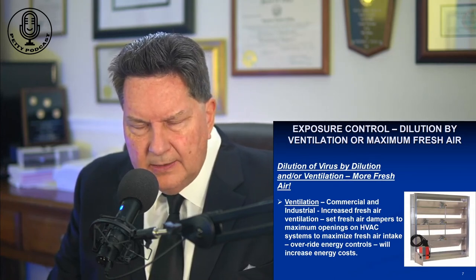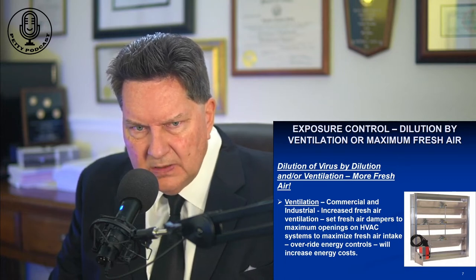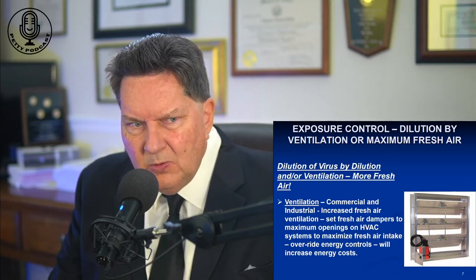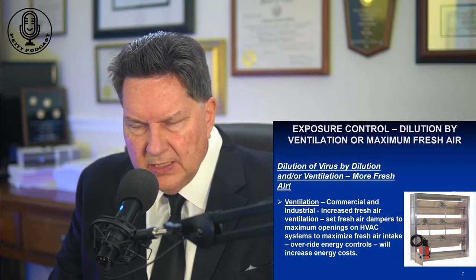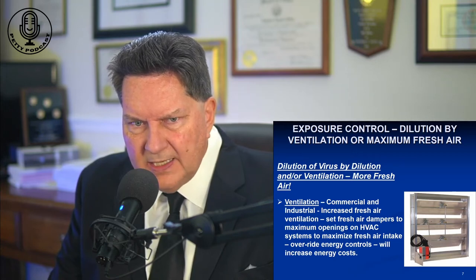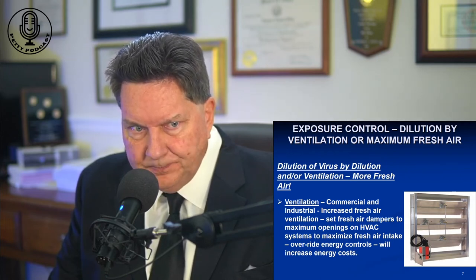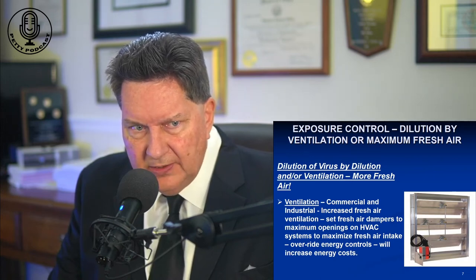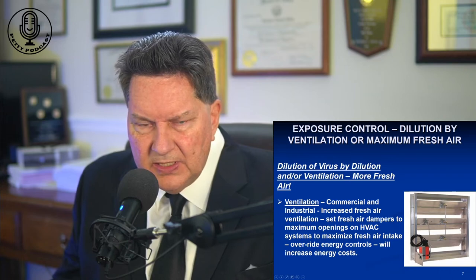The other way in industrial and commercial buildings — this may be a topic you're not as familiar with — is that HVAC, or heating, ventilation, and air conditioning systems in large buildings have what they call fresh air dampers. These open and close to allow less or more fresh air into the building. With energy codes, a lot of these dampers are set to have minimum opening, because fresh air takes more energy to treat — to cool it, heat it, and remove the humidity. What designers have done in recent decades is decrease fresh air into spaces. In this time, one thing we can do is override those dampers to ensure maximum fresh air into the building, even if it overrides energy codes, until we get this crisis behind us.